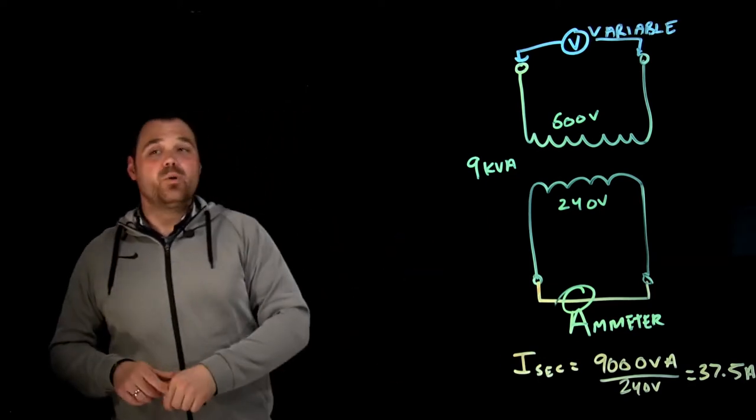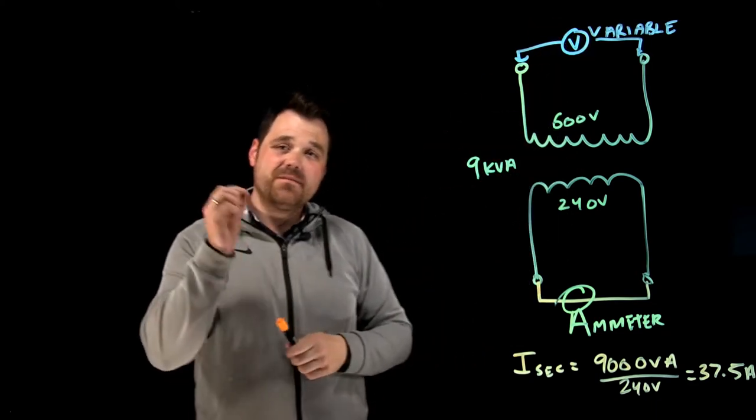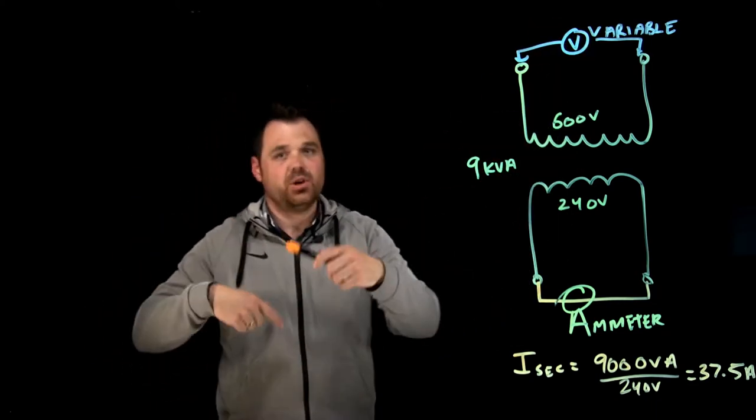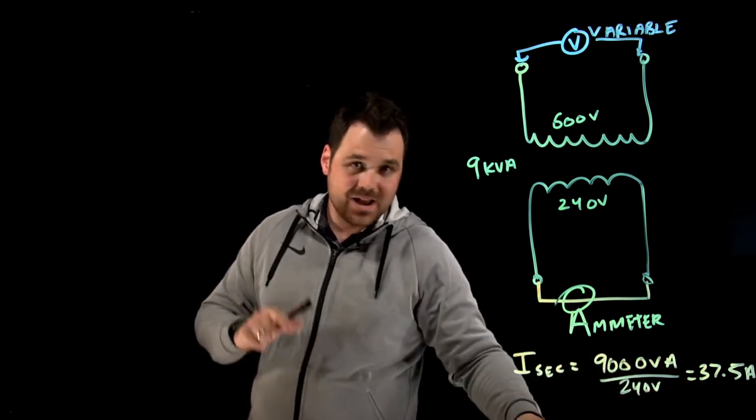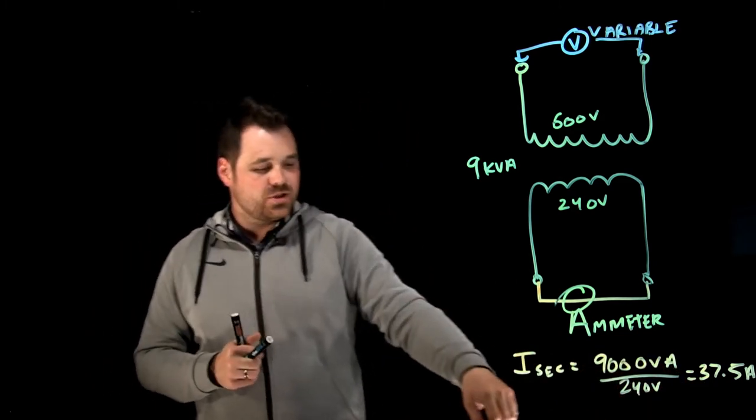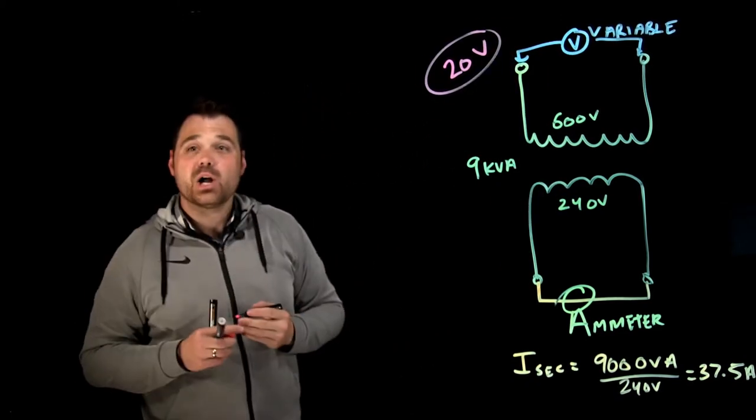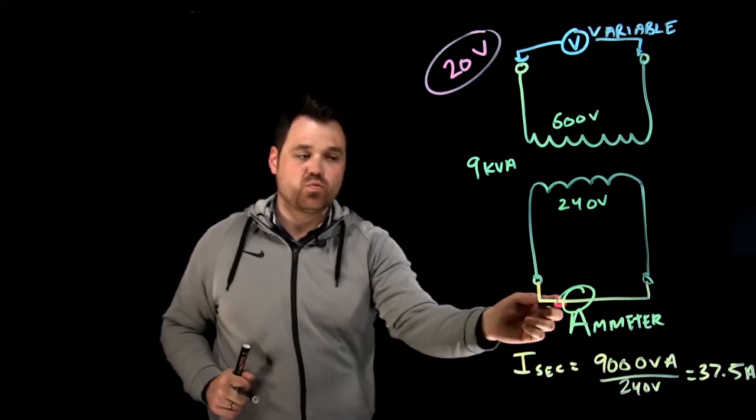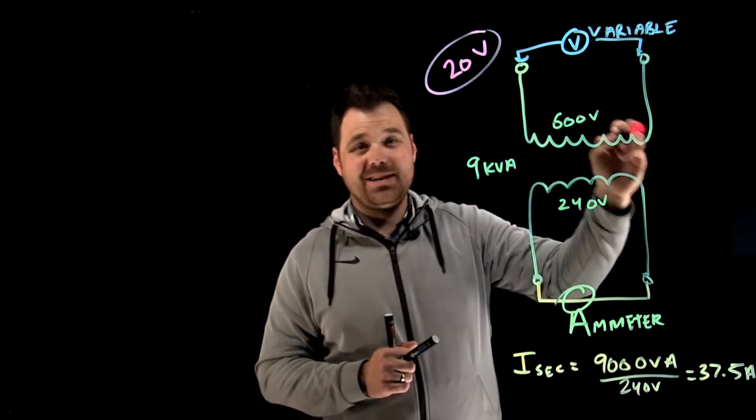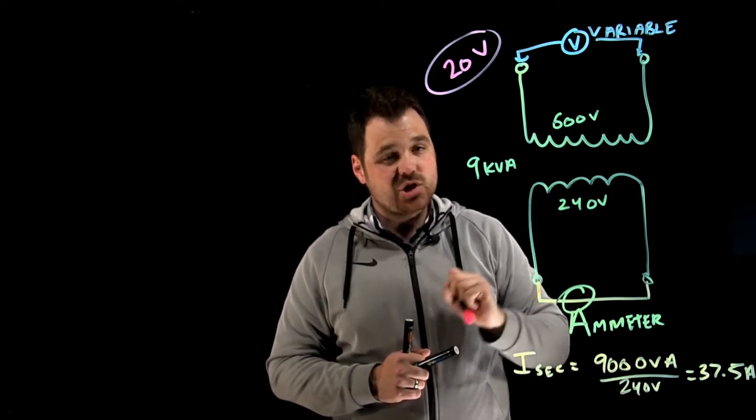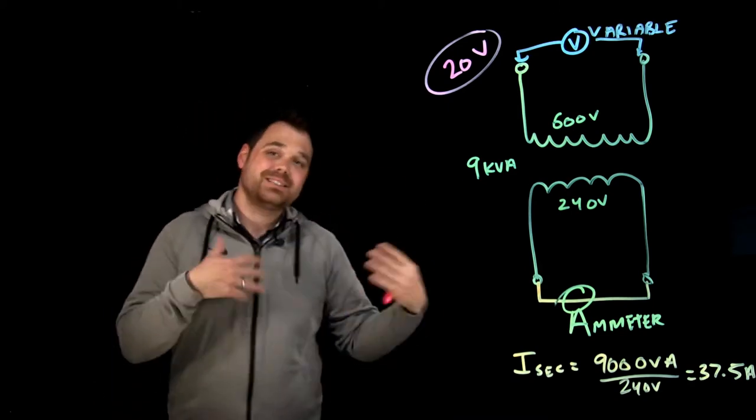So what I want to do is I'm going to short circuit, hook up my ammeter, and slowly start increasing that voltage on the variable voltage supply. That's going to go up, it's going to go up, it's going to go up. Eventually, I'm going to reach 37.5 amps on my ammeter. That's when I stop. And now let's say just for our conversation here today, let's say that number was 20 volts. That's what I got on my voltage supply in order to reach my rated secondary current. That is the amount of voltage required to overcome the impedance of the transformer to get my rated secondary current.